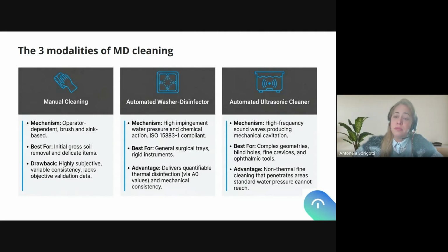And after, last but not least, we have the automated ultrasonic cleaner, where the mechanism is high-frequency sound waves producing mechanical cavitation. It is best for complex geometries, blind holes, fine crevices, and ophthalmic tools. The advantage of ultrasonic cleaning is that it penetrates areas that standard washer disinfectors cannot reach.